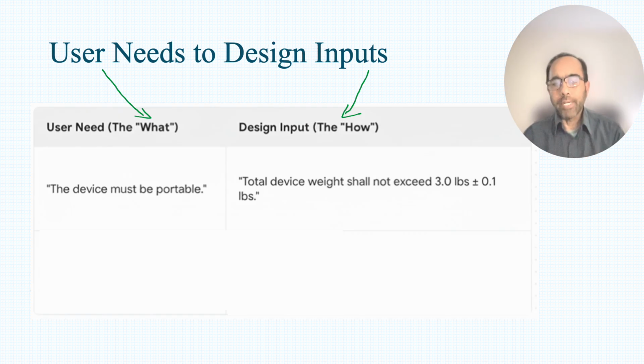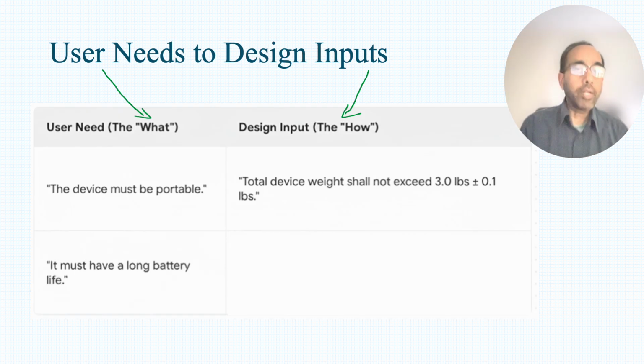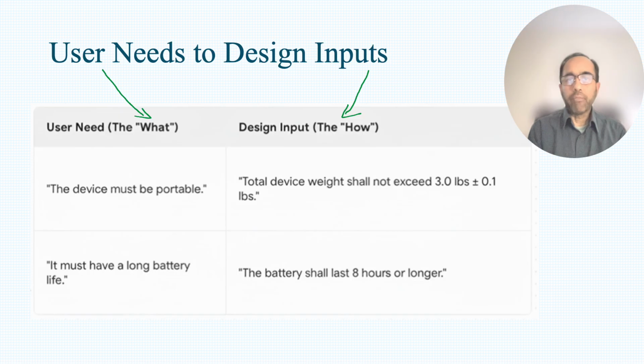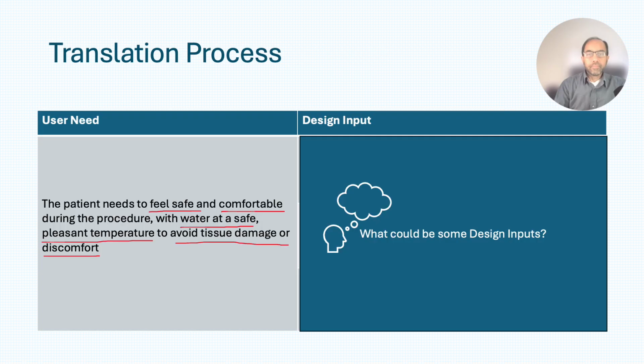Or there might be a user need that says the device must have a long battery life. That is also subjective, right? So in design input, you translate that into something like the battery life shall be 8 hours or longer. Converting those user needs into design inputs or engineering specifications, even though it's fun and rewarding, requires some skills and training and team effort. Why? To ensure that design requirements are captured clearly and precisely to avoid mistakes down the road.